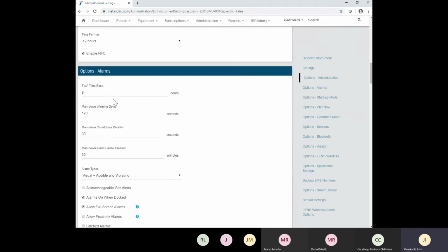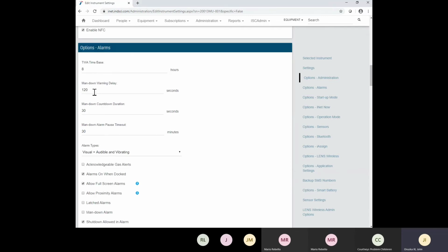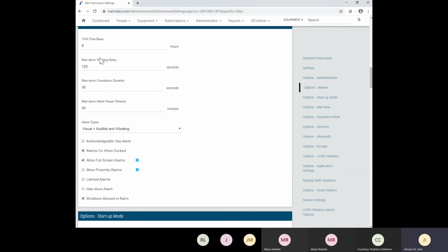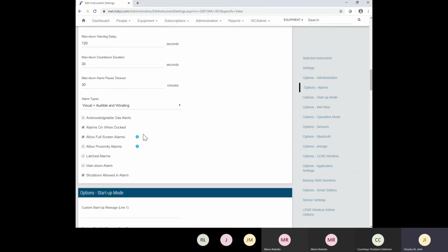As you come down, here's your TWA alarms that I was talking about. This is where you can change the time base. You can change it from like an 8-hour period to 10, 12, whatever you want to change it to. And as we come down here as well, this is where we can do some of the other changes, such as alarms on when docked.